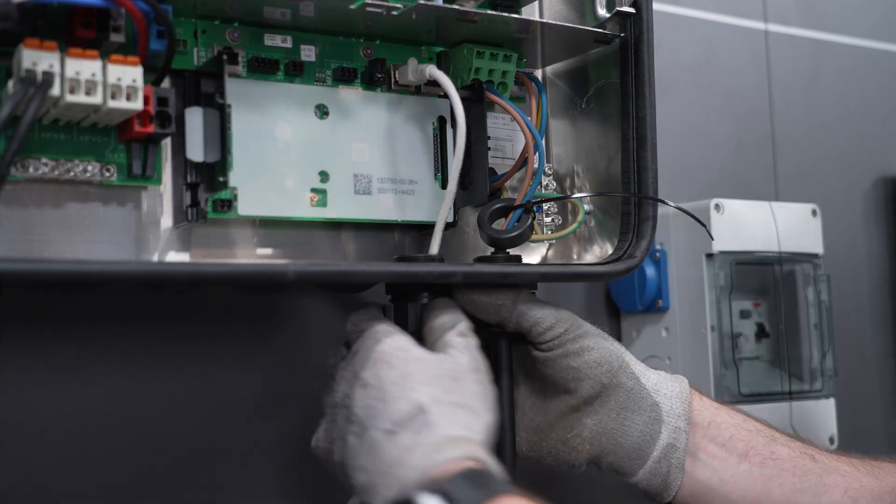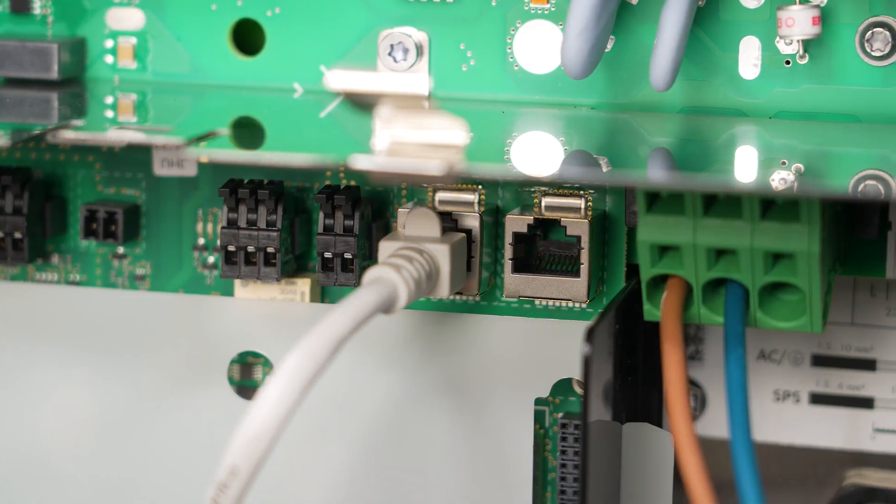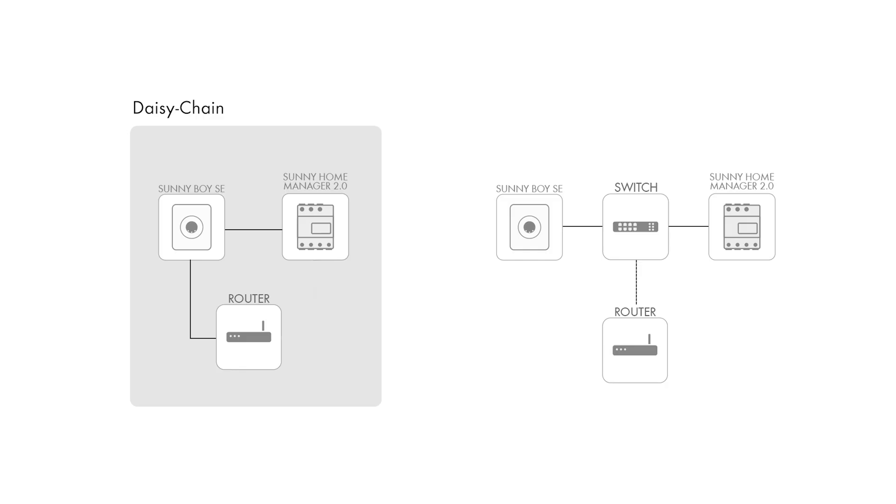Tug slightly on the cable to ensure that it's securely in place and ensure that the cable does not touch the AC cables. LAN 1 and LAN 2 can be used flexibly to connect the communication. These can also act as a switch, allowing you to connect several devices as a daisy chain.